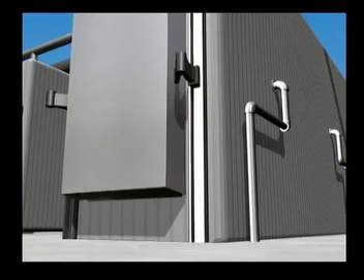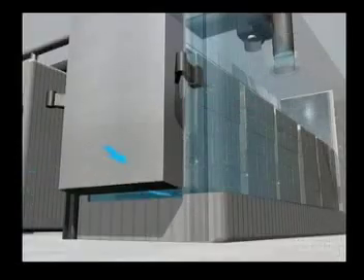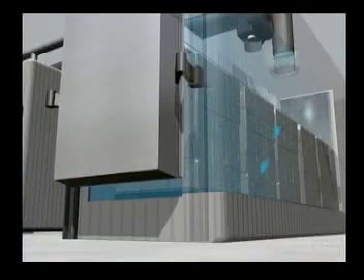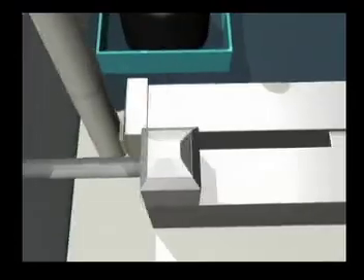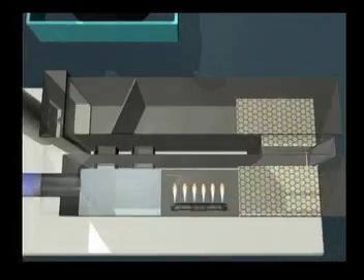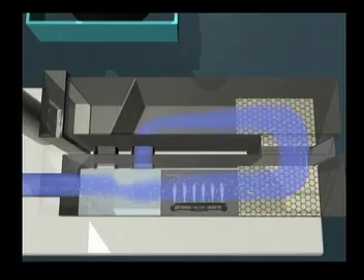The front door is raised a few inches, which automatically opens the vent at the rear of the chamber. Air is drawn through the chamber to another pollution control device called a catalytic oxidizer. Once the air enters the catalytic oxidizer, it is heated as it passes over open flames. Any remaining traces of ethylene oxide are removed as the air passes over a metal catalyst. After the chamber has been ventilated for several minutes, operators can safely enter to remove the products.